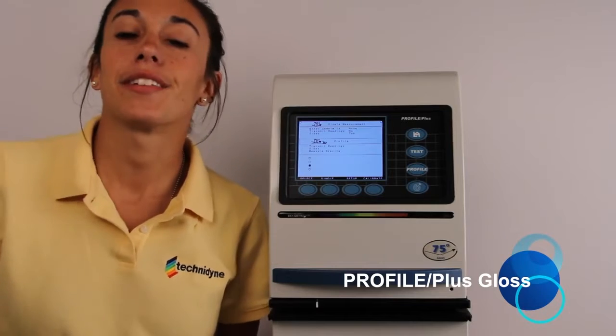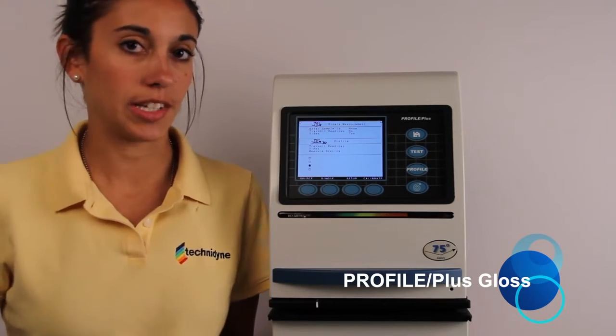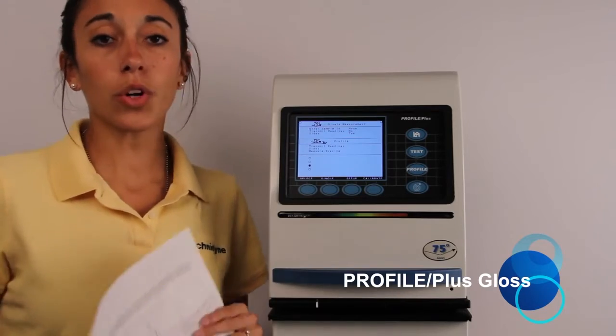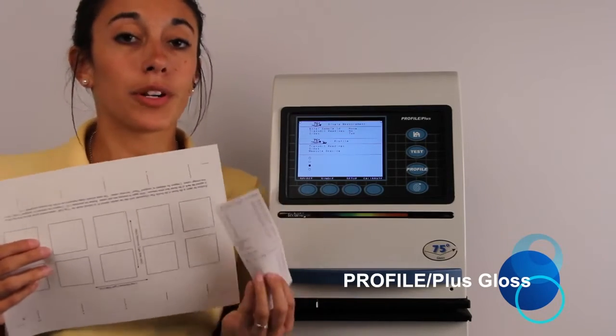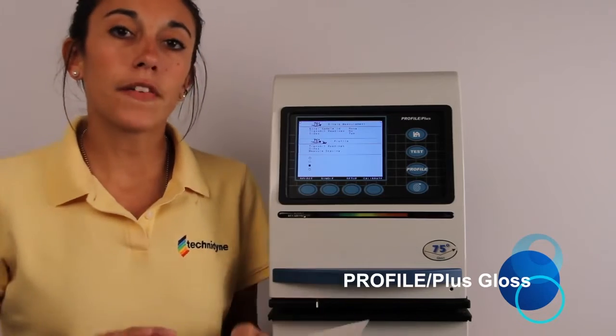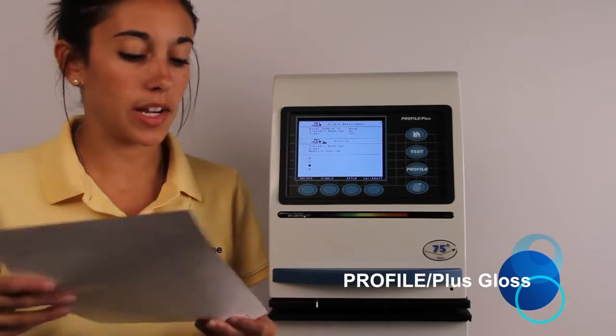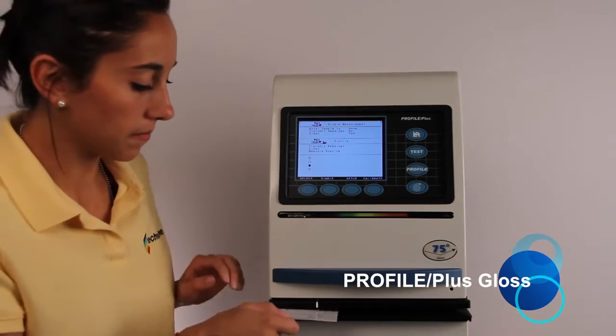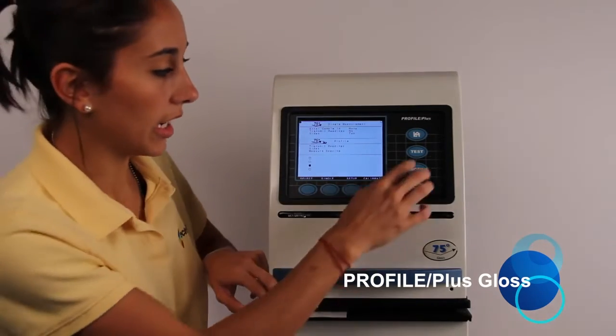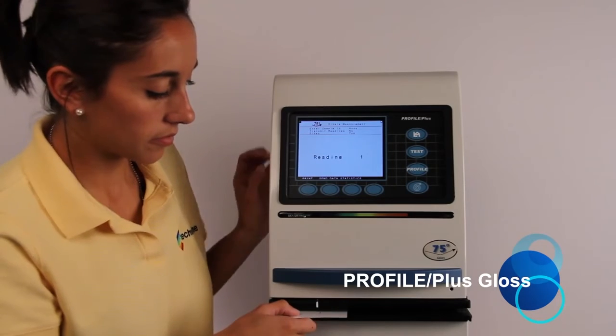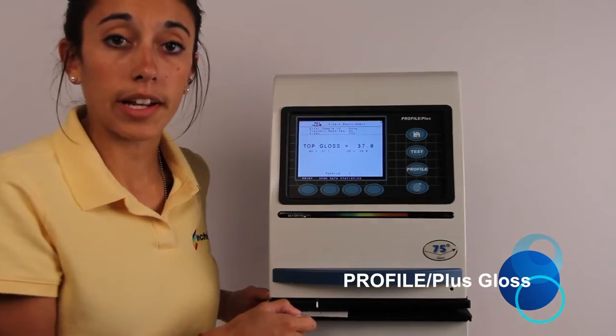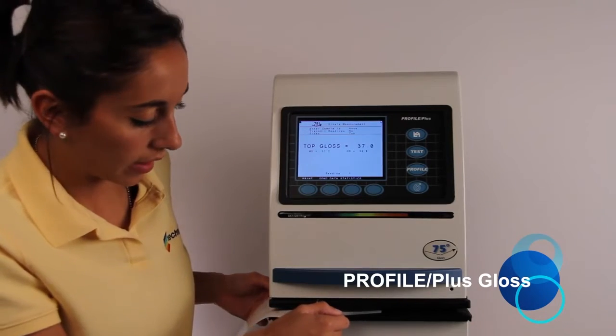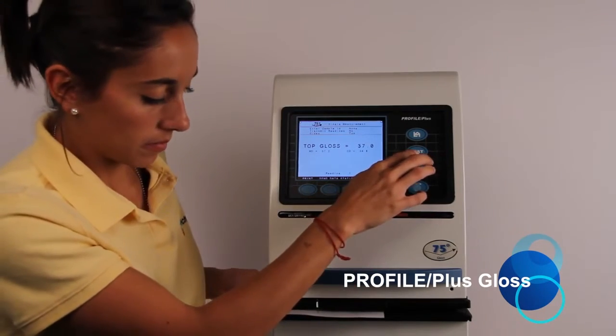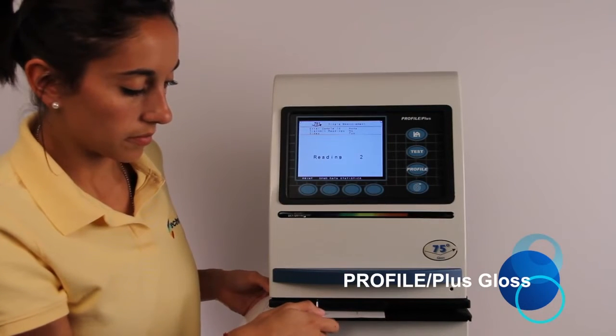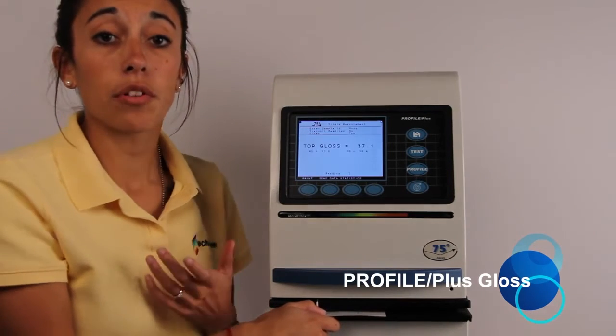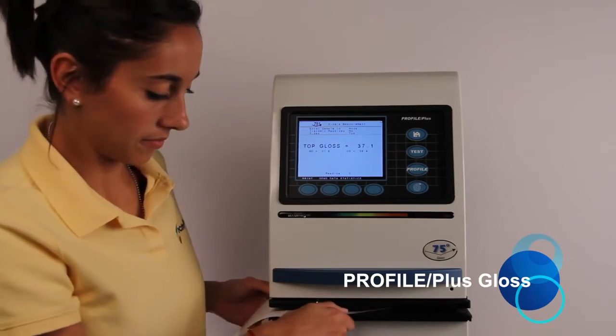The second way to verify calibration is with the paper standard linearity verification sheets. There should be an A and a B. We're going to use A, so it's important to make sure that you have the corresponding printout that goes along with it. The first thing that you'll want to do is find the number 1 and line it up on the instrument with the white line. And you'll press the test hard key. Once it's done reading, you'll move over so that the 2 is lined up with the white line, and you'll press the test hard key again. You're going to do this all the way around from numbers 1 through 10.